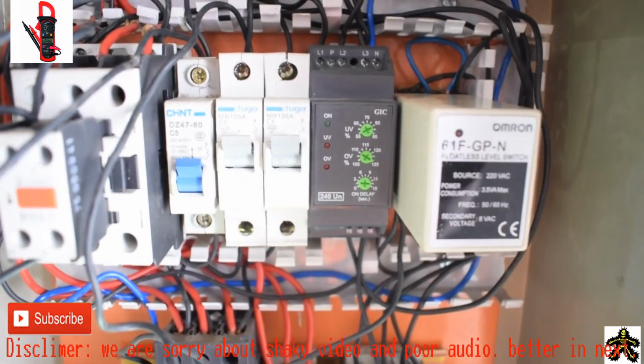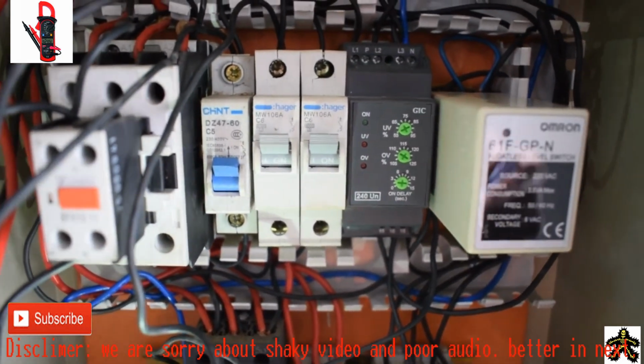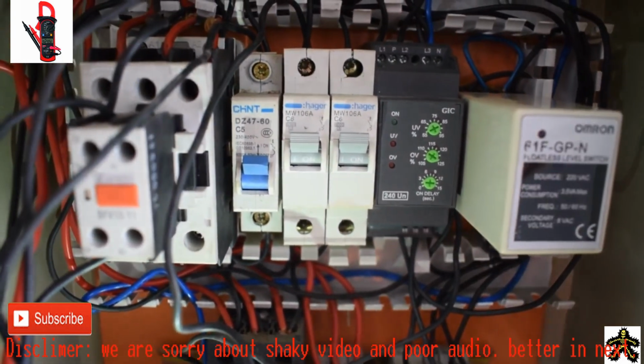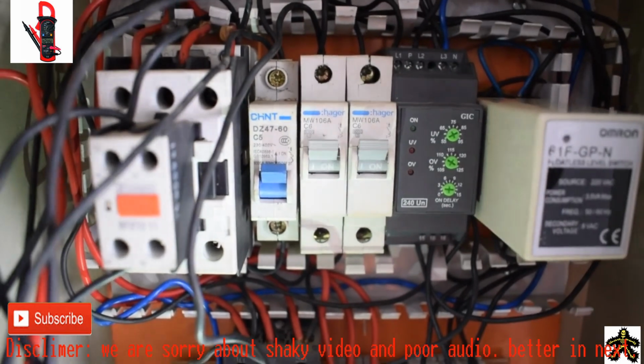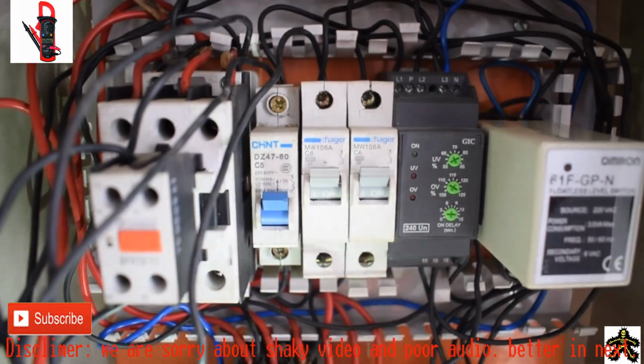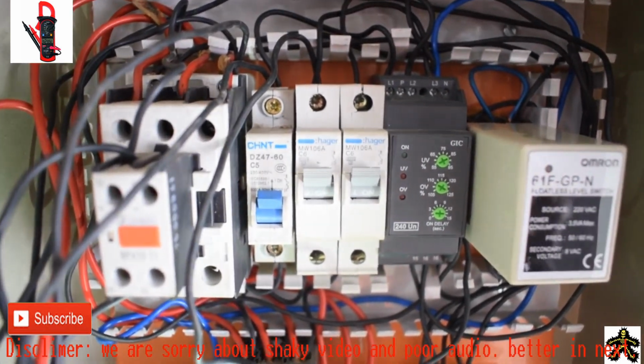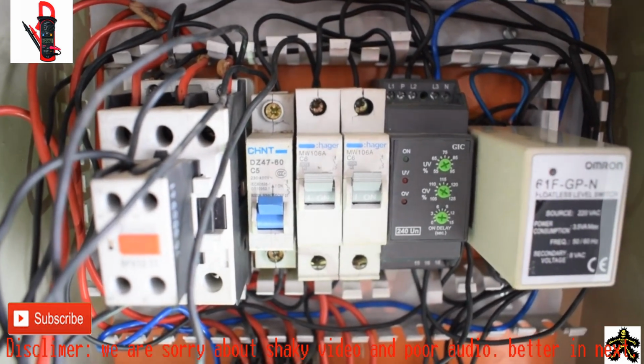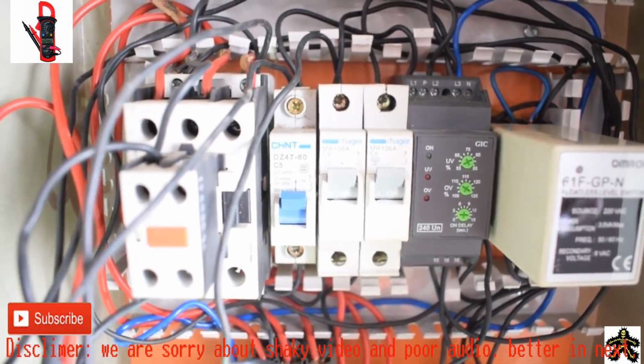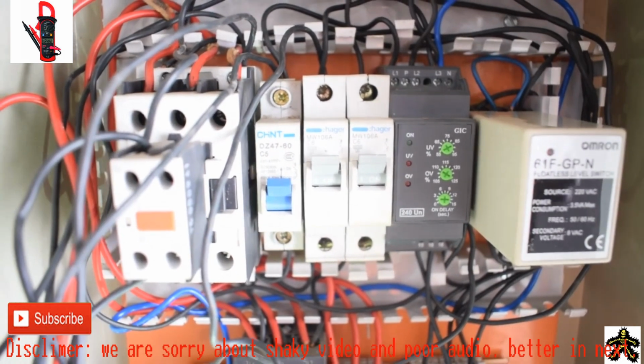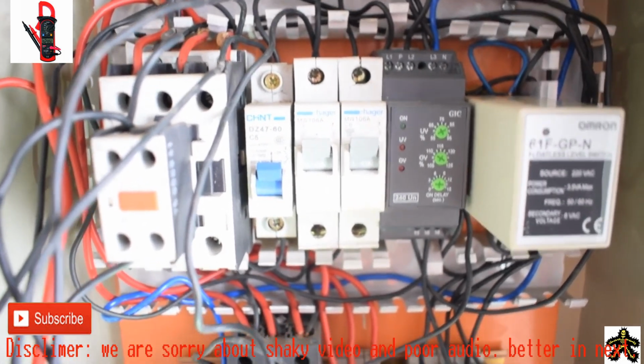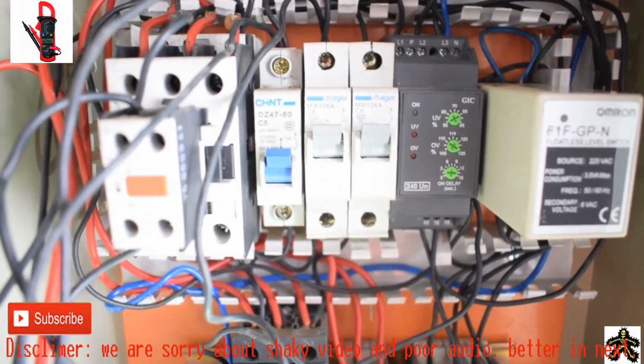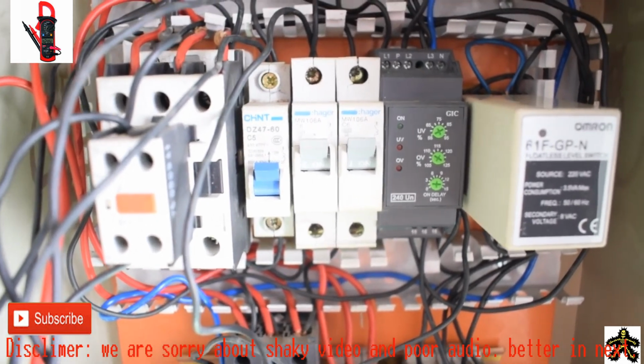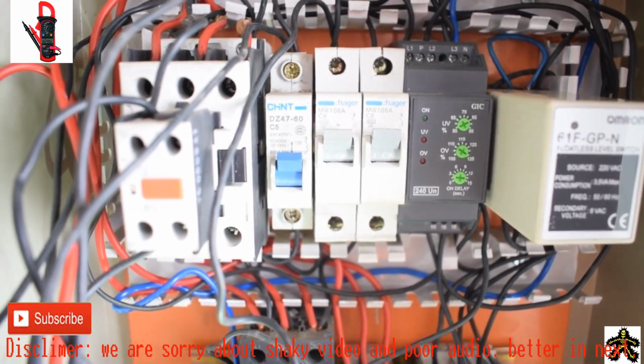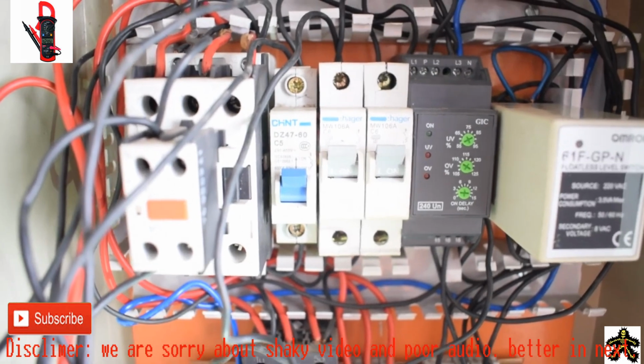The under voltage setting means you can set the threshold such that if power on a certain phase goes down to a certain threshold, the circuit will be off. Remember, if one phase is out, there is an imbalance in the circuit, especially in a motor circuit, and you will lose your motor.